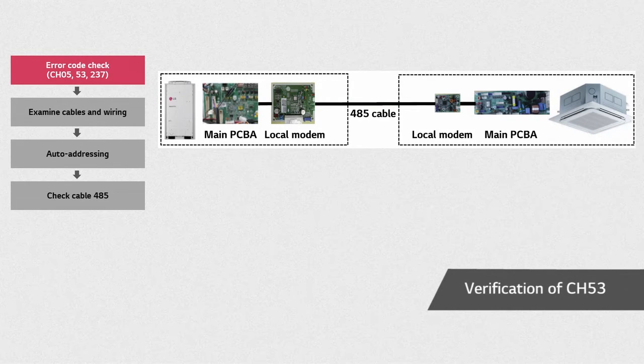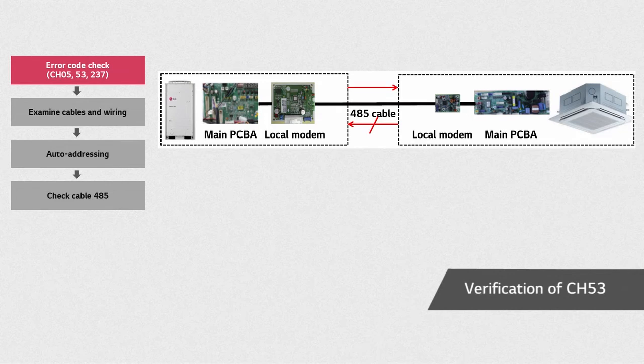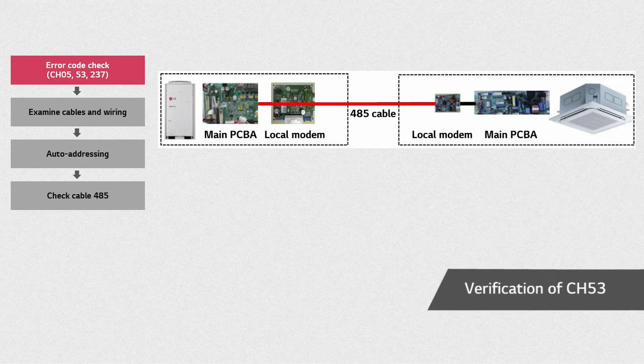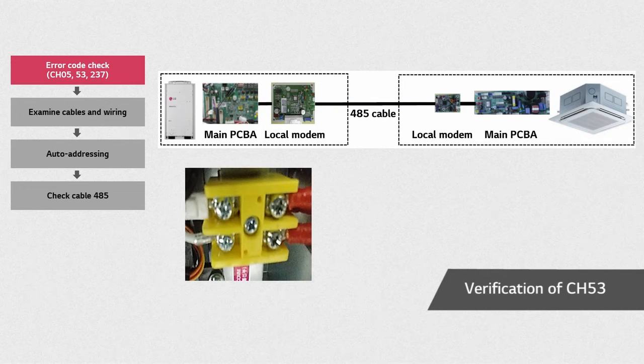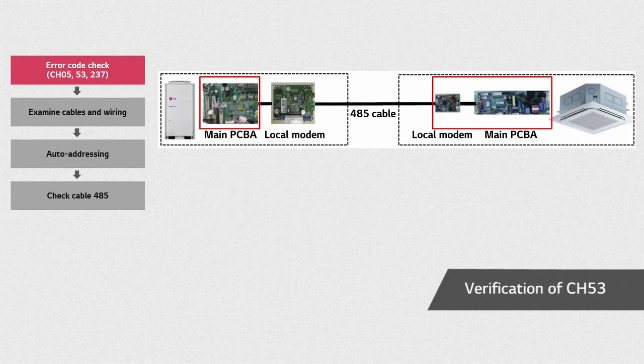Let's talk about error CH53. This error will occur regardless of the IDU and ODU being in Gen2 or Gen4 mode. CH53 occurs when the ODU sends data to the IDU but the ODU cannot receive any signal. When error CH53 occurs, first, check if the 485 cable between indoor and outdoor units is properly installed. Second, check if the communication cable is loosely or not connected to the block terminal. And third, check if there is any local modem or main PCB error.